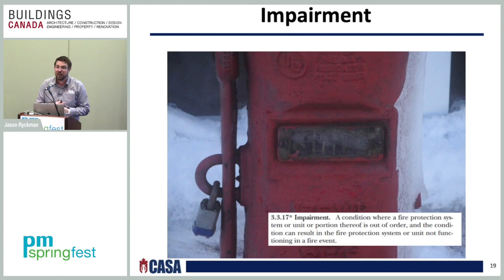If your system is impaired, you've got to get it fixed, because heaven forbid a fire occurs in your building and your system is impaired, you're going to have to go in front of a judge and explain why your system is not up and running. I don't know about you, but I've been in court before. It's not fun. So make sure your system is not impaired. That picture shows an impairment just by doing a visual examination, an inspection, which anyone can do with a little bit of knowledge of the system. This says "shut." If you see any valves that say shut, you better ask questions on why that valve is shut, because your system is probably impaired. So make sure that system is up and running.